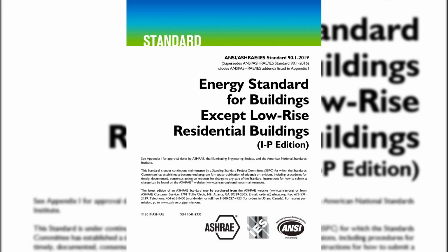6.2.9. Heating and cooling design parameters for load calculation systems must be designed in accordance with several standards, including Section MC 312 of the 2022 NYC Mechanical Code, ANSI, ASHRAE, ACCA 183/2007, and ASHRAE 90.1/2019. When energy recovery systems are used, heating and cooling loads need to be adjusted to account for the resulting load reductions, as per Section C403.1.1 of the 2020 New York City Energy Conservation Code, NYCECC.